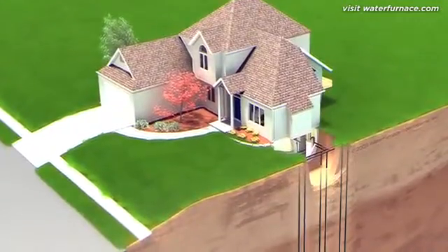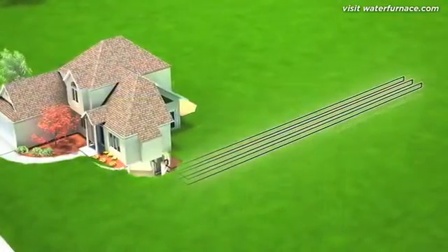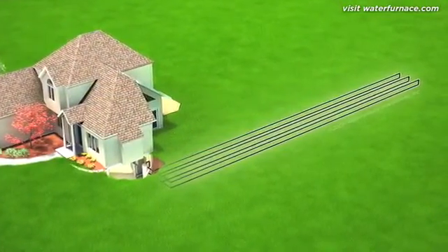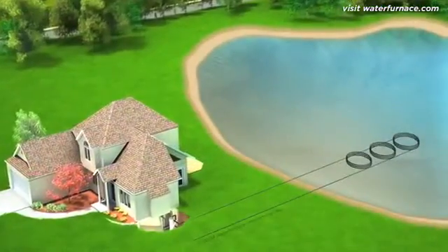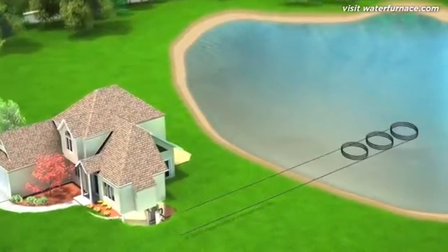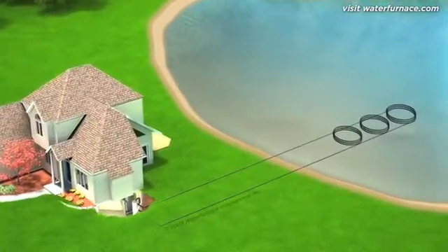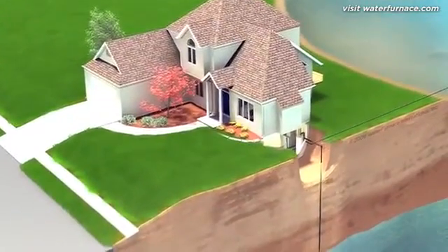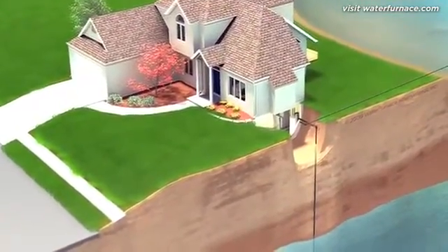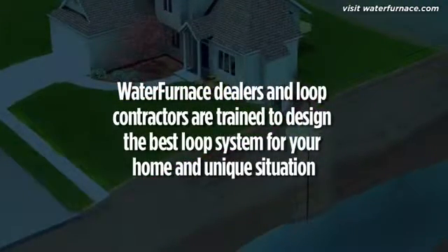Well-drilling equipment is used to bore small-diameter holes from 100 to 400 feet deep. Horizontal loops are generally preferred where more space is available — pipes are placed in trenches that range in length from 100 to 400 feet. If a nearby body of water is available, it can be utilized for a pond loop; coils of pipe are simply placed on the bottom of the pond or lake. Open-loop systems are an option if water is plentiful and low in minerals, using groundwater from a well as a direct energy source. WaterFurnace dealers and loop installers are trained to design the best loop system for a particular home to ensure optimum performance.